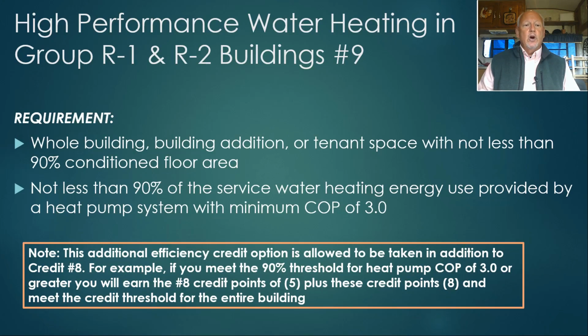I just want to note that this additional efficiency credit is allowed to be taken in addition to credit number 8. So for example, if you meet the 90% threshold for a heat pump COP of 3.0 or greater, you will earn the number 8 credit points, which is 5, and then these credit points, which is 8, and meet the entire credit threshold for the entire building. So there's an incentive there for buildings of group R1 and R2 where they could meet their entire additional efficiency credit option with these service water heating additional points.